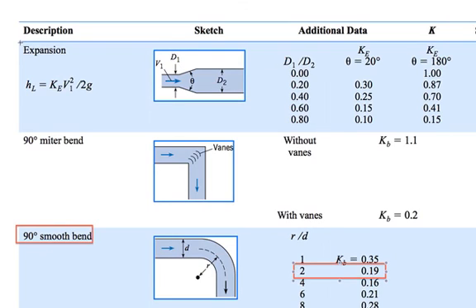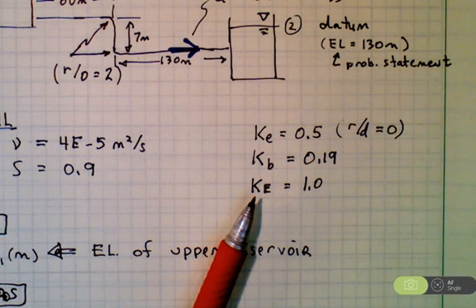For the exit, use the expansion here. Theta is 180 degrees. D2 is effectively infinity, so the ratio of d1 to d2 is 0. And so you look right here, and the minor loss coefficient is 1.0, corresponding to an angle of 180 degrees. All right, document the minor loss coefficients. Notice the use of subscripts.